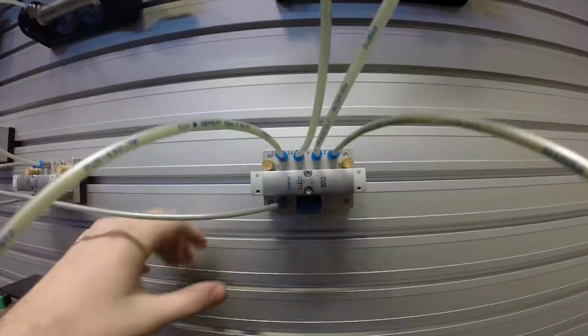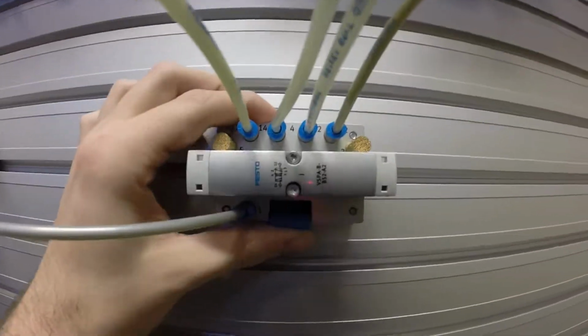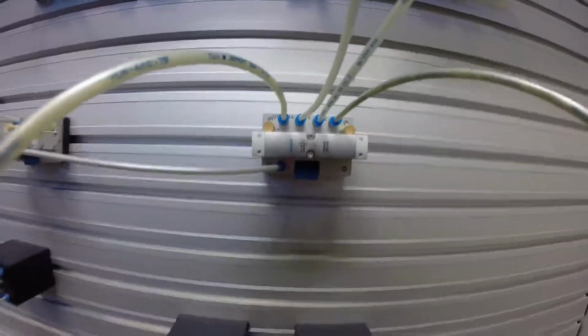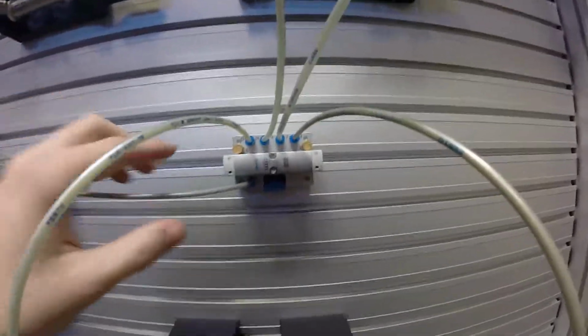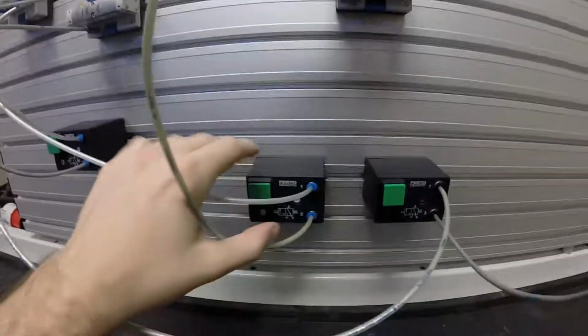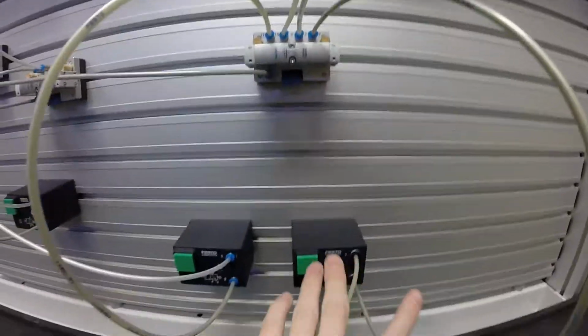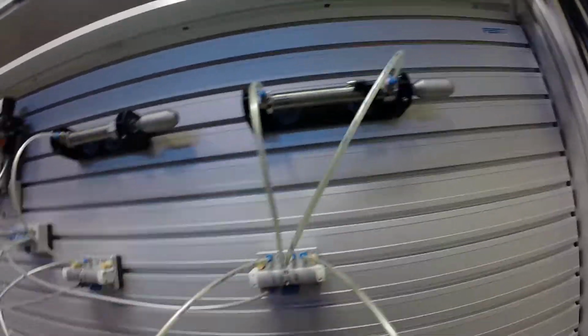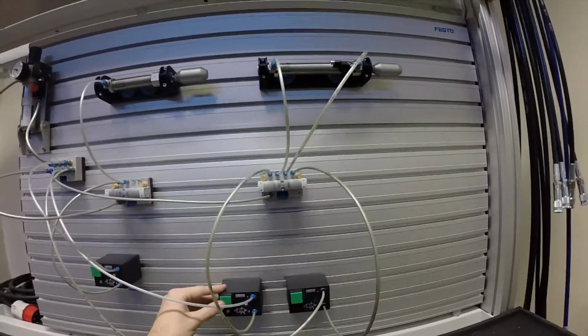If we take that over here, what we've got is our 5-2, which is pilot operated and pilot returned. You'll see that from the diagram here. Both sides have that triangular symbol for the pilot lines, so I need to give a pulse on either side to operate it. We've got a 5-2 valve there, one side is operated by a 3-2, another side is operated by a 3-2, and then we've got our two outputs, which control our double acting cylinder. And you'll see this in operation here.